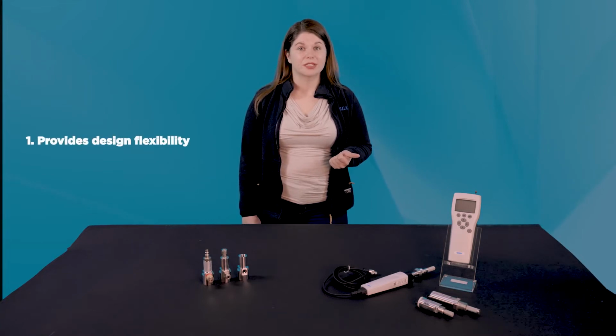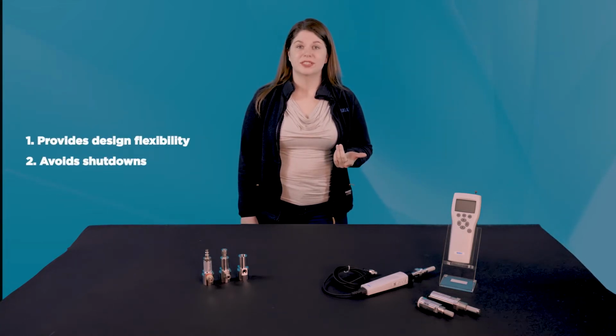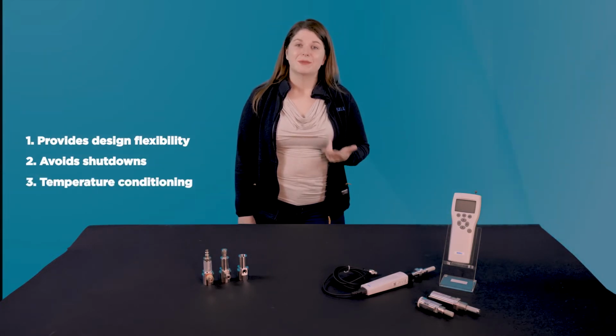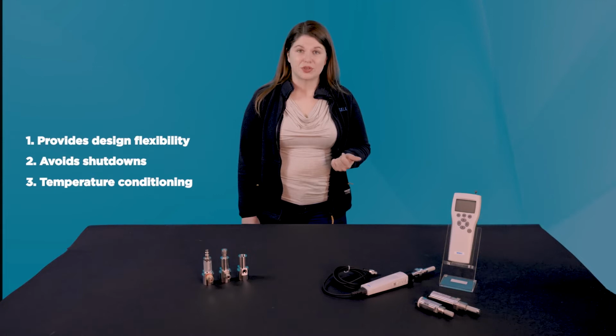Dew point probes are often installed directly into a system with a simple threaded connection, but if you are installing into a pressurized system, this usually involves a system shutdown, which can be time-consuming and costly. Using a sample cell addresses many challenges you might face when installing a dew point transmitter. Using a sample cell provides piping and system design flexibility, can enable you to avoid system shutdown during installation, and provides an opportunity for cooling when air is too hot for the sensor. I will walk you through the different sample cell options in a minute, but first let's review some best practices when installing a dew point transmitter.